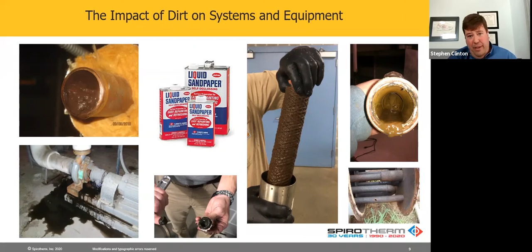Now, in our industry, typically, traditional methods have not been full flow. Traditional methods have been sidestream. Maybe 10 to 15% of that flow is used and it's taken through a bag filter, a cartridge filter, maybe through a sand filter, or possibly a cyclonic filter. In some of those systems, you can get out different size particles, things like that. The nice thing about our unit is that we can remove 80% of particles 30 microns and larger in just 100 circulations. In a closed loop system, we can get down to 5 microns in size. 8 microns is a red blood cell, just to give you an idea.